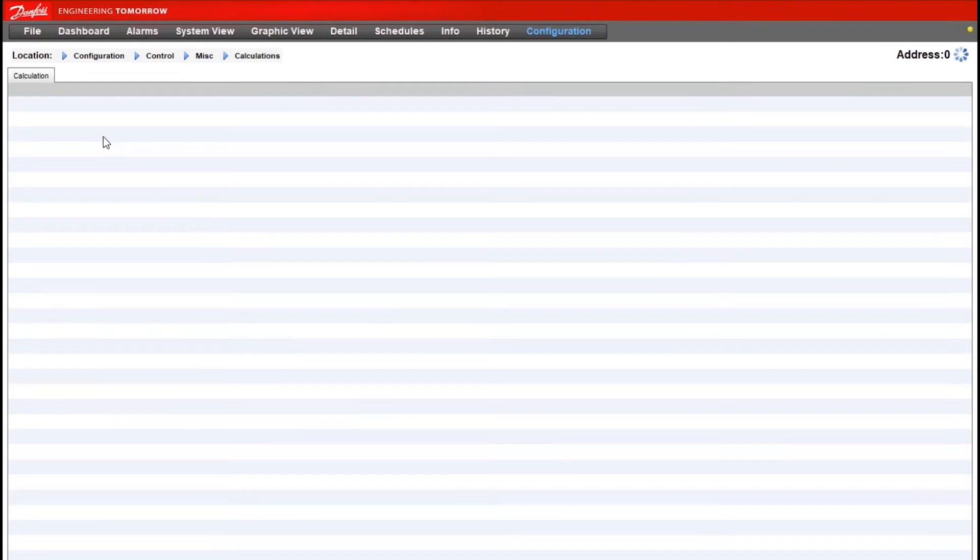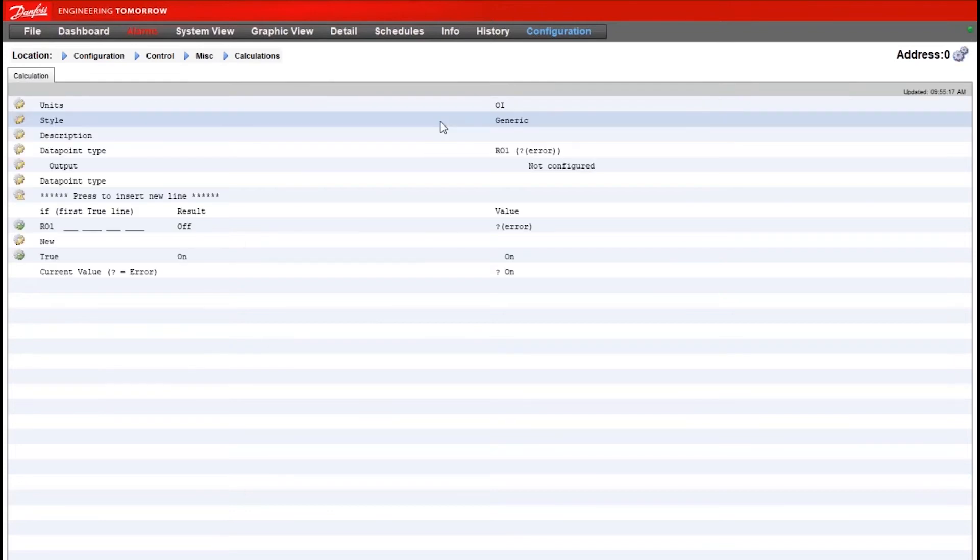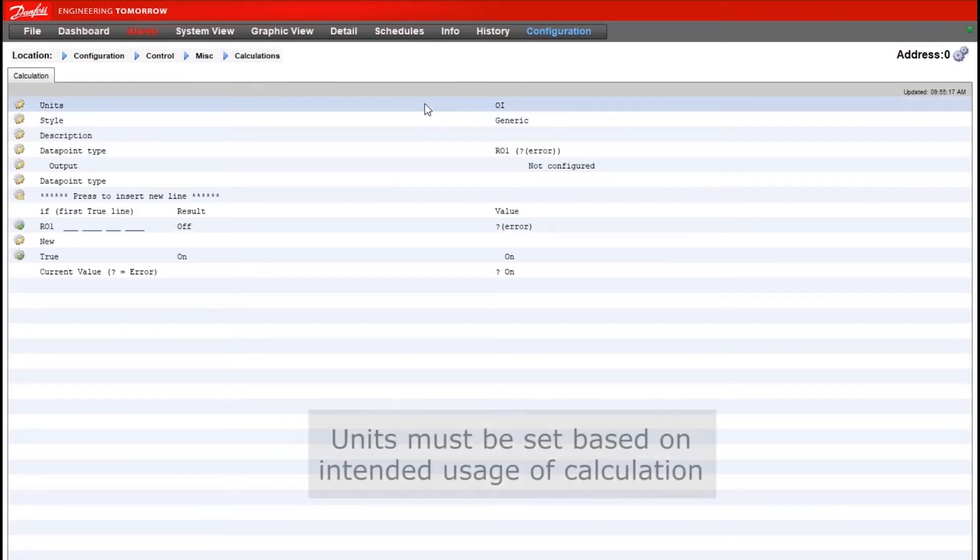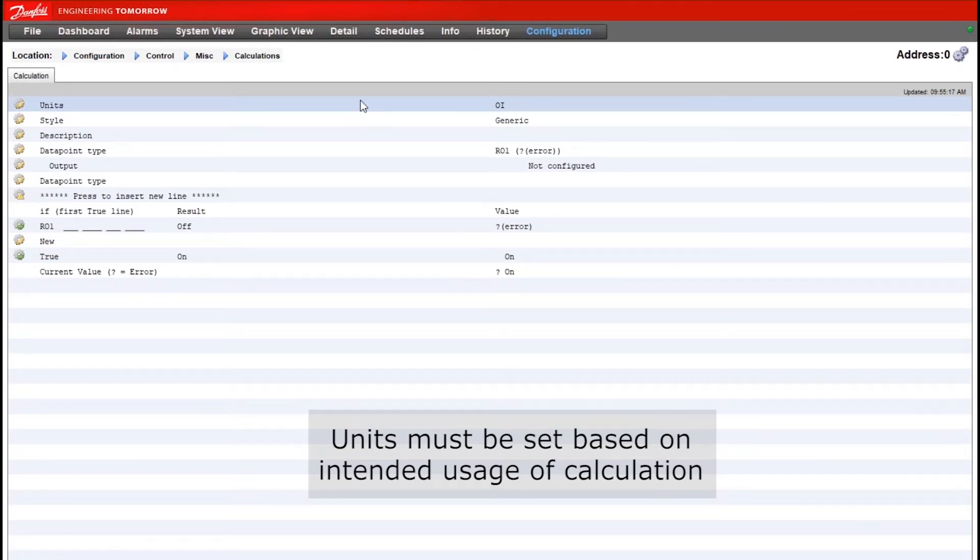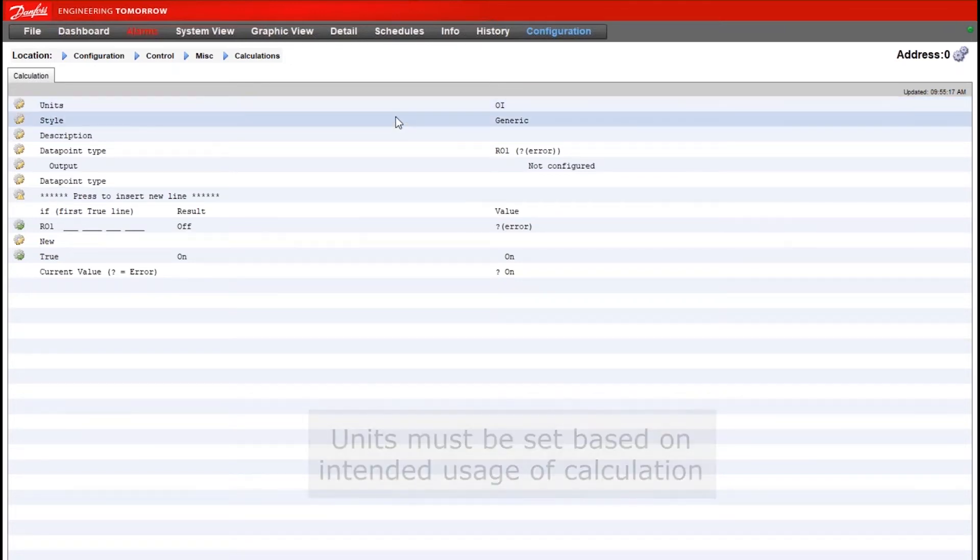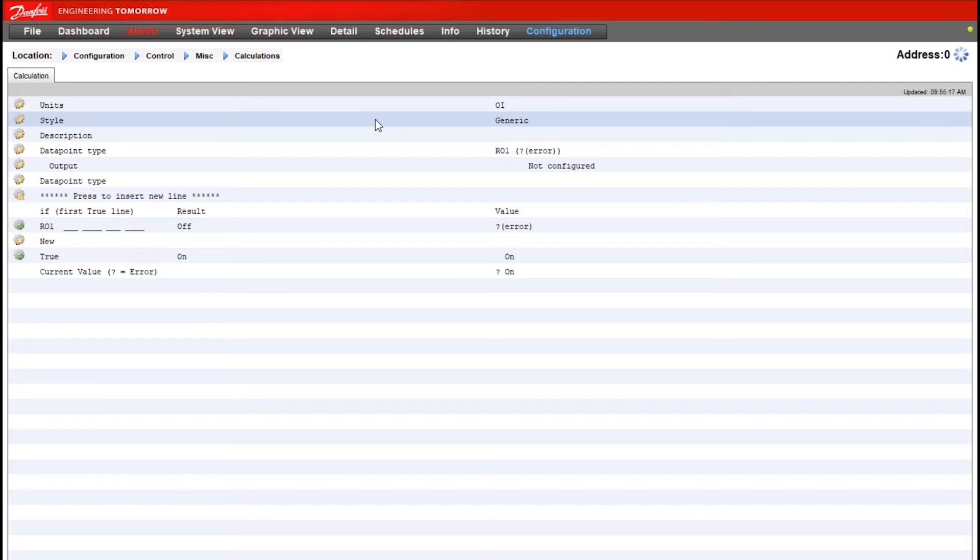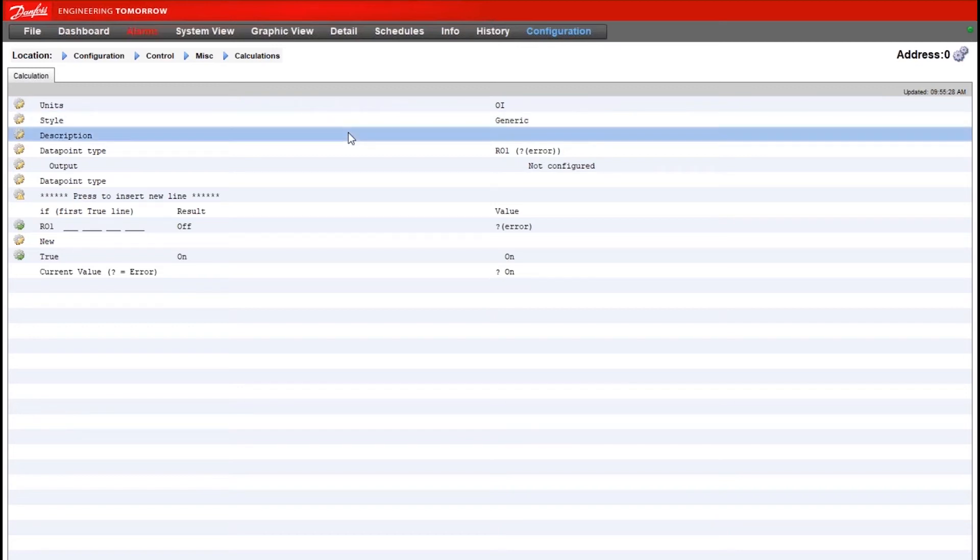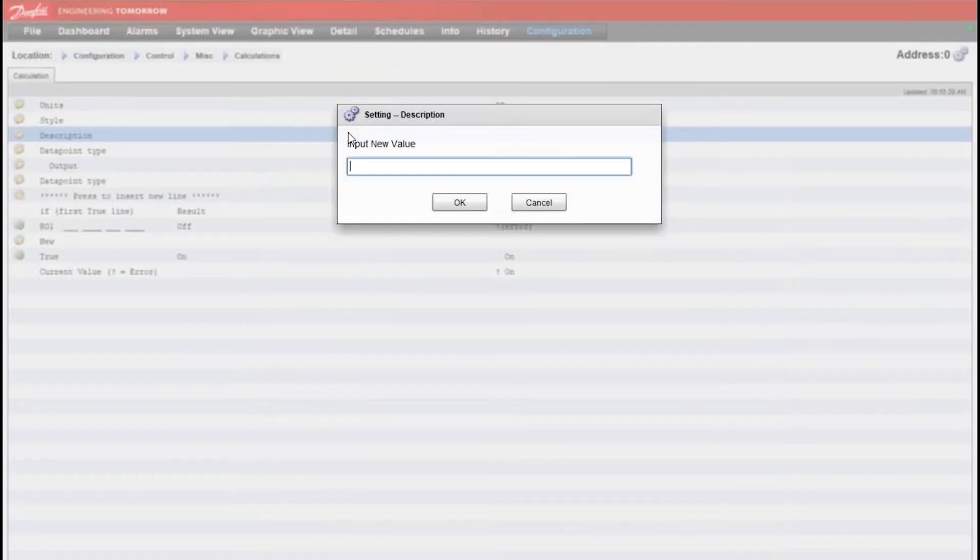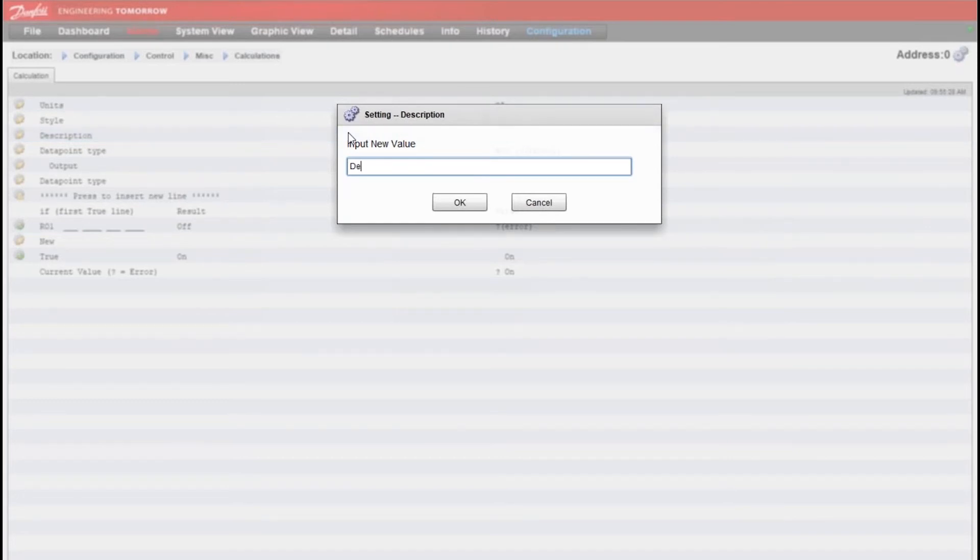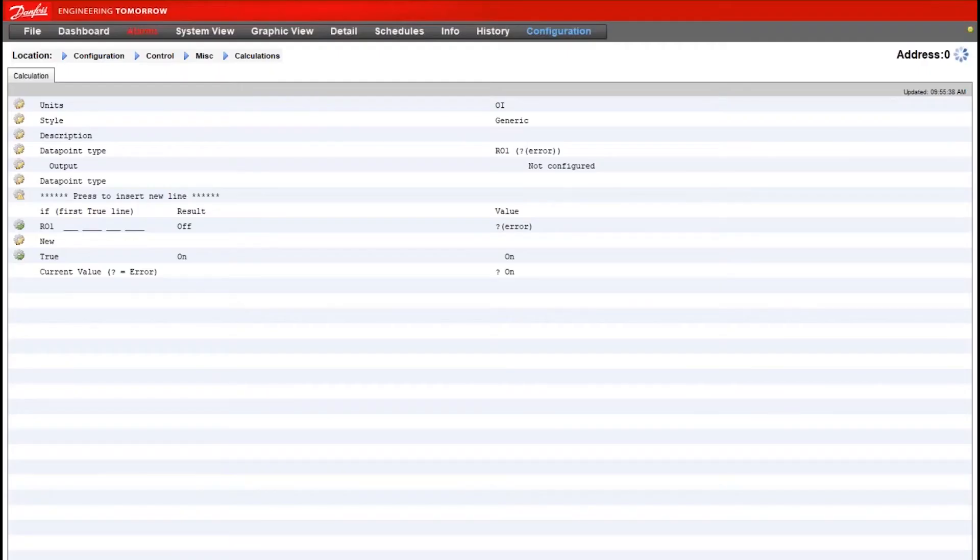Here we can enable a new calc. We will double click on that calculation to get into the setup of it. Our units here, we would be looking to turn something on or off with this logic, so we want to leave units as OI. Style will leave as generic. There's not necessarily a predefined template that would use any of the specific styles that are options here. Description you would name based on however you're using this calculation to control a point in the system manager. We'll just call this defrost calculation for this exercise.